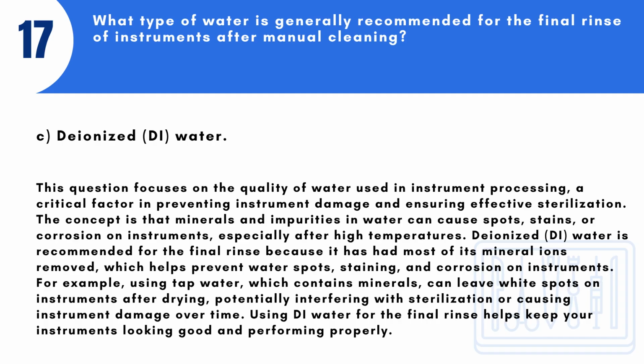This question focuses on the quality of water used in instrument processing, a critical factor in preventing instrument damage and ensuring effective sterilization. The concept is that minerals and impurities in water can cause spots, stains, or corrosion on instruments, especially after high temperatures. Deionized (DI) water is recommended for the final rinse because it has had most of its mineral ions removed, which helps prevent water spots, staining, and corrosion on instruments. For example, using tap water, which contains minerals, can leave white spots on instruments after drying, potentially interfering with sterilization or causing instrument damage over time. Using DI water for the final rinse helps keep your instruments looking good and performing properly.